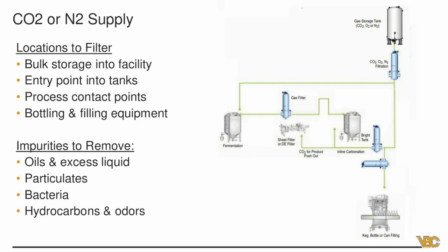In terms of locations to filter, bulk storage into your facility, whether you do it immediately at the bulk tank or you wait till inside the facility and find a closer point, either of those locations is good. Next would be entry points into tanks. If you're doing tank to tank movement and counterbalancing via CO2 or nitrogen to cap off the extra space, when you're injecting that into the tanks, that's when you would really want to filter it prior to that.